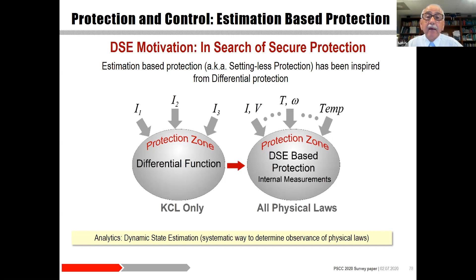So we extended this idea and said, why don't we use all the measurements we take in a protection zone, a generator, a transformer, and so on, such as voltages, temperatures, speed, depending on the device, and then see if the measurements are consistent with the mathematical dynamic model of the device to be protected. Basically, we compare the measurements to the detailed dynamic model of the device to be protected. The best way to do that is through dynamic state estimation. The result of the dynamic state estimation tells us either that the measurements fit the mathematical model of the protection zone, or that they do not, in which case it indicates an internal fault, an internal abnormality, and so on.